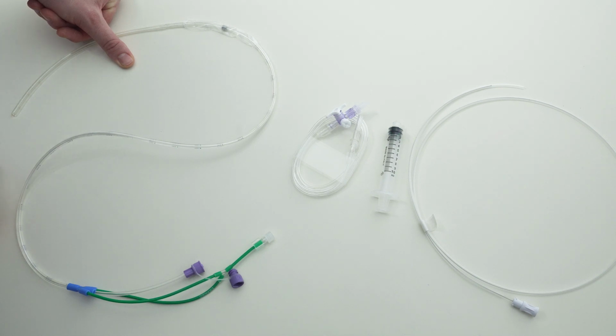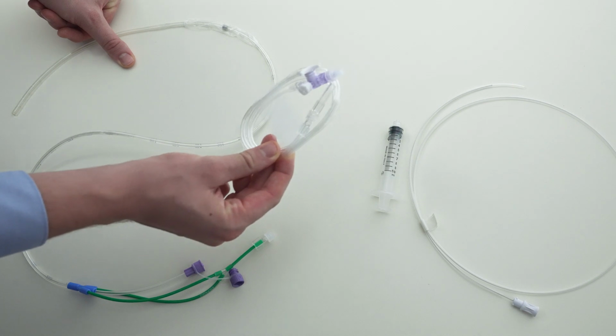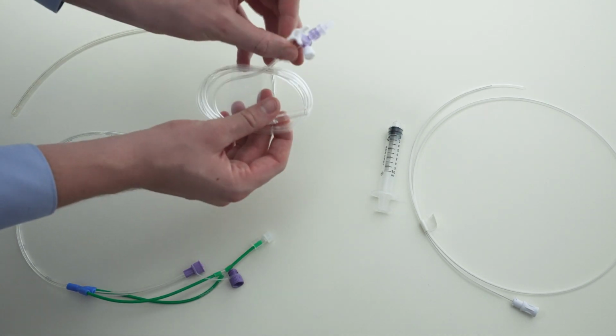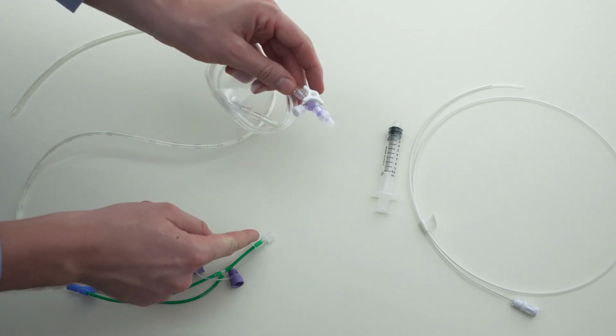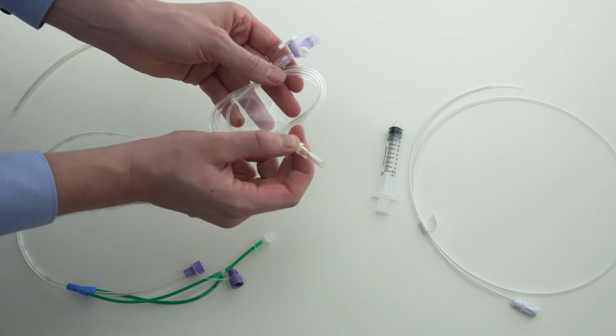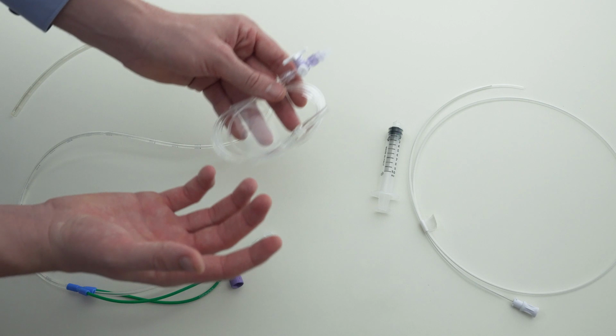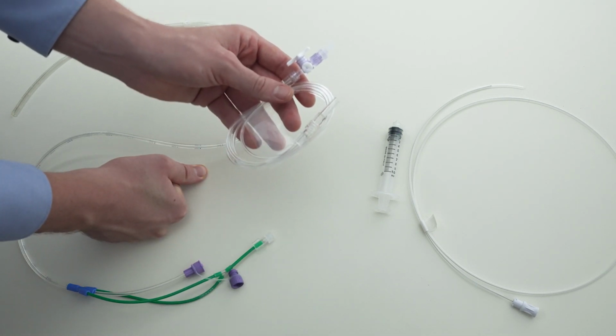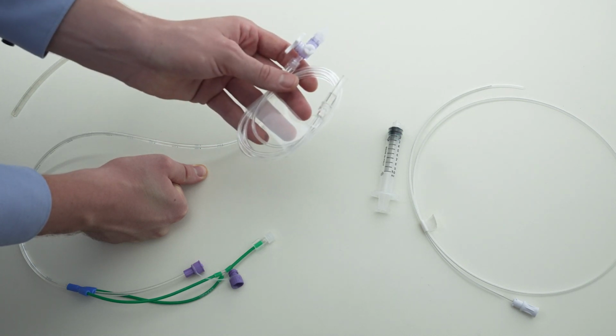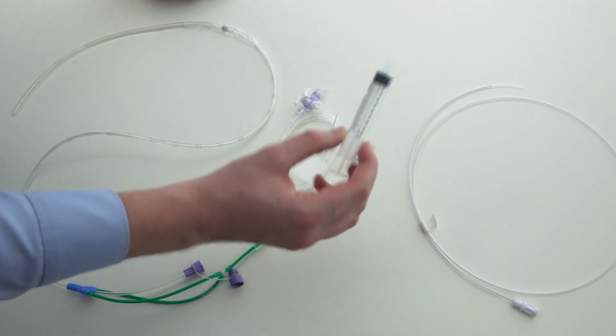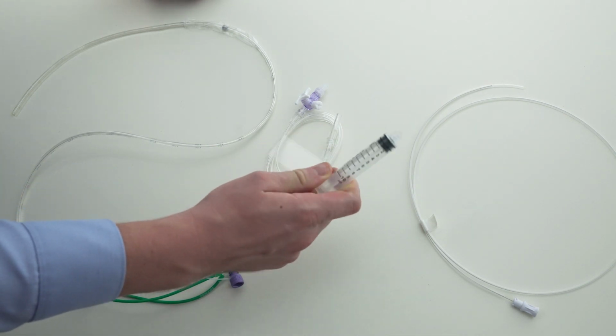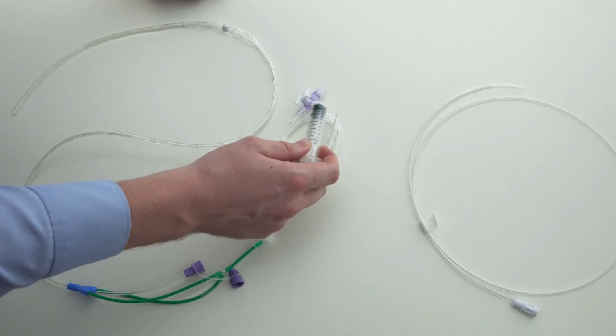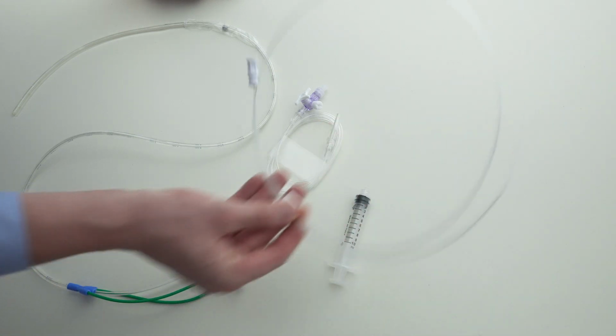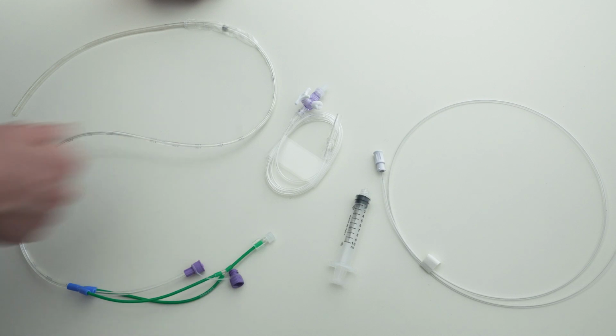take a chest X-ray. What's also in the package is this connection piece. It comes with stiff tubing. It has a three-way valve with luer locks that you will connect here to your esophageal balloon, and this piece over here will connect to the module, the esophageal and transpulmonary pressure module made by Getinge, which will be inserted into your mechanical ventilator. Moreover, there's a 10 milliliter syringe with a luer lock that you can use to fill the balloon after connecting it through the three-way valve over here. And lastly, there is a guide wire included in the package that you can use to place in the nasogastric feeding catheter before you insert it in your patient, to help in making the insertion go as smoothly as possible.